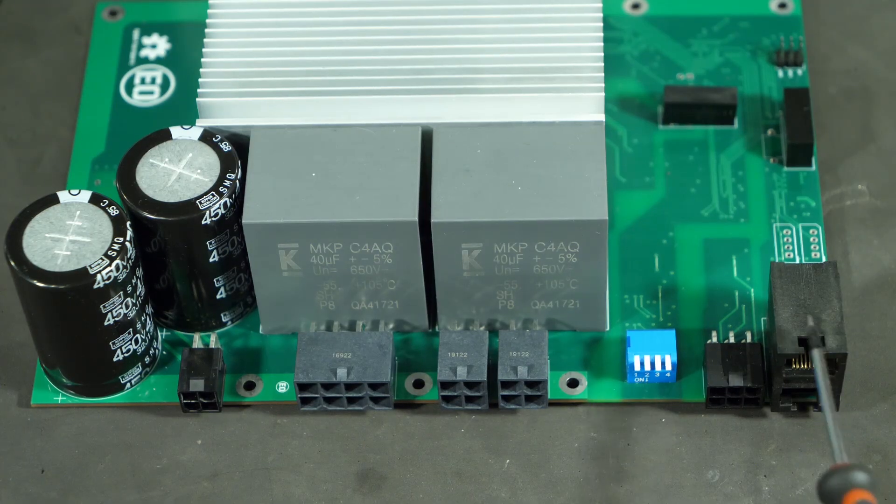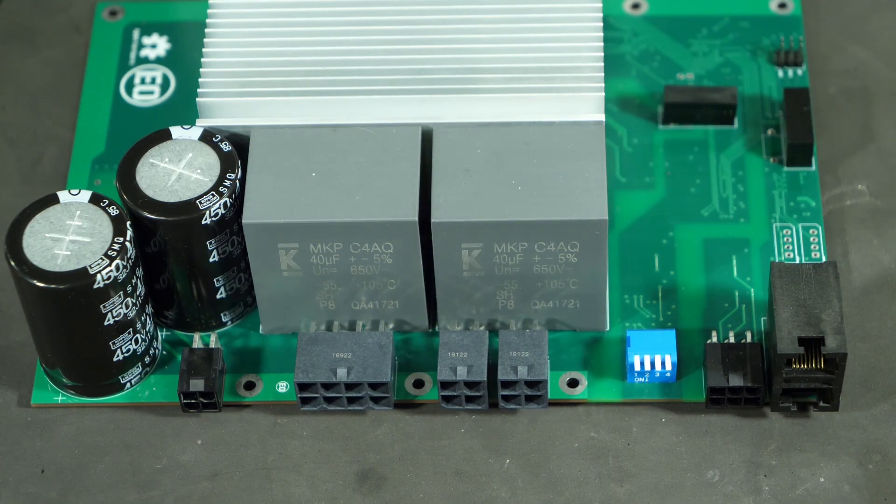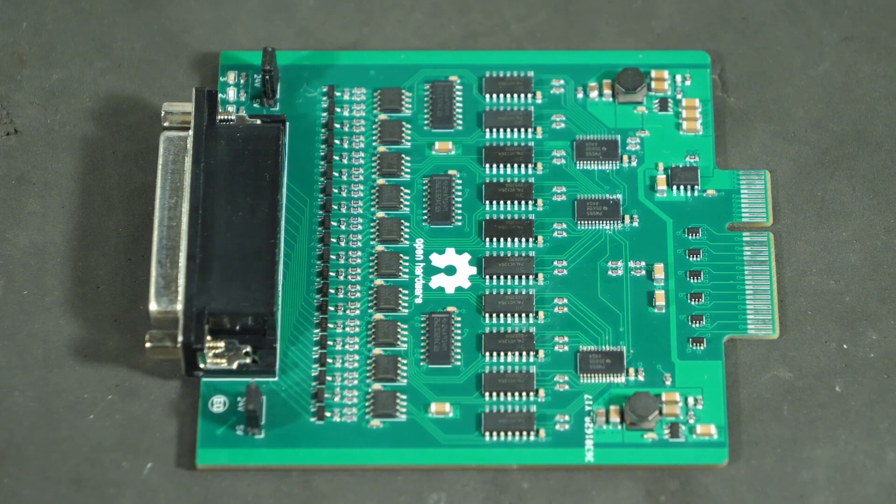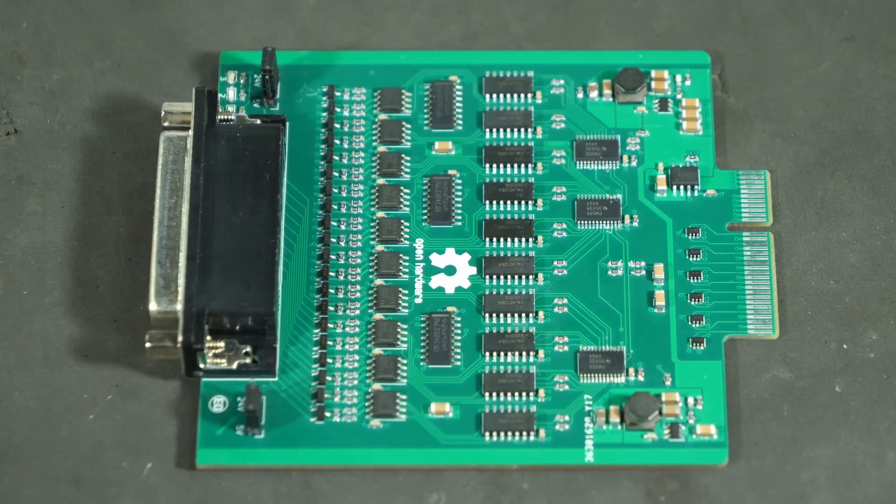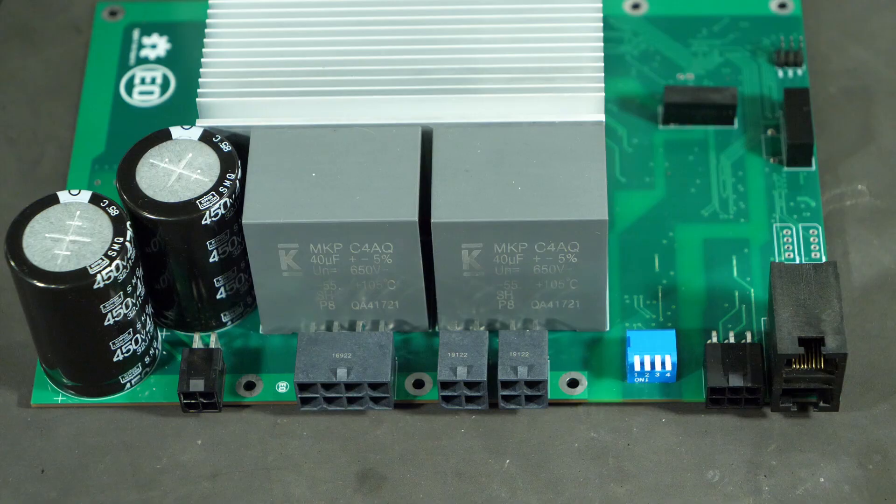The first two connectors over here are RJ-45 jacks, which allow the drives to plug into one another so they can be daisy chained, and then also plug into the board we looked at previously. This is where the drives get their 24-volt logic power, and also where they get the RS-422 communication to interface with the main processor.